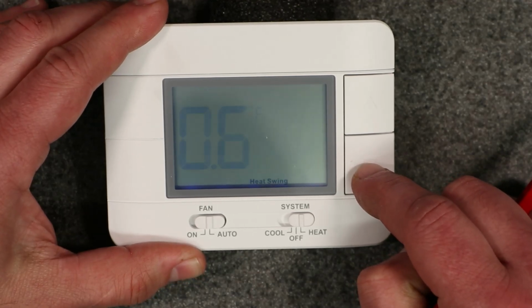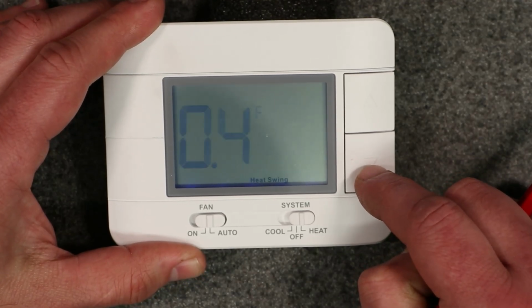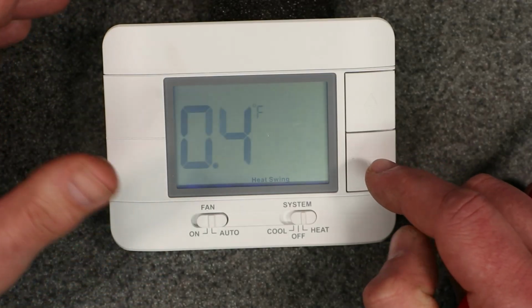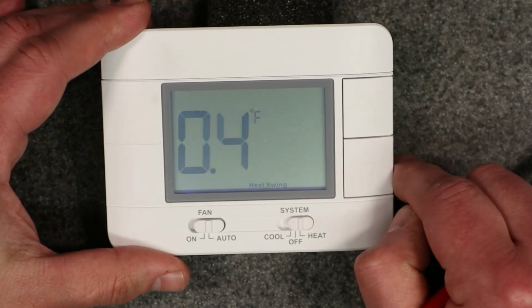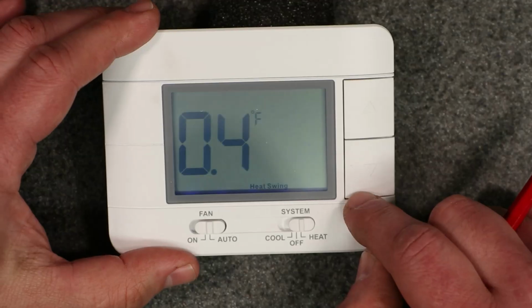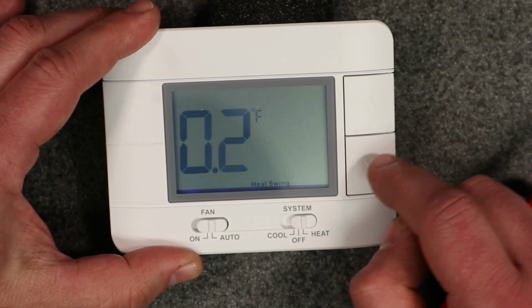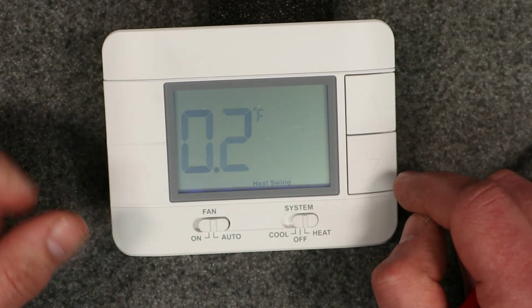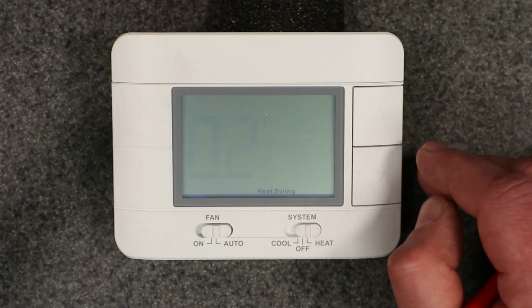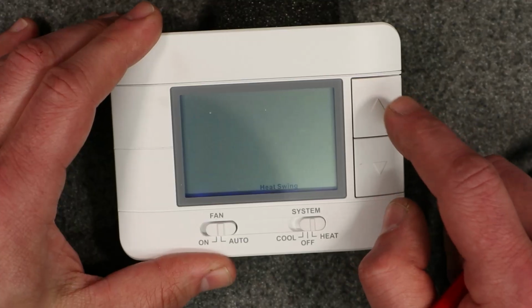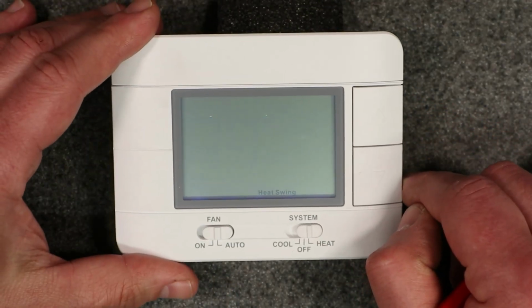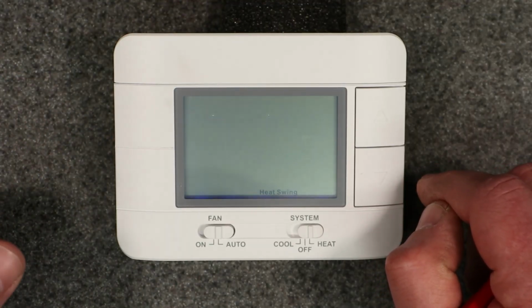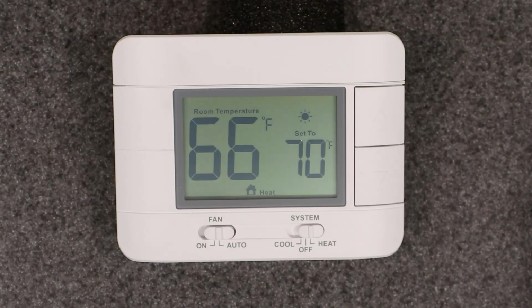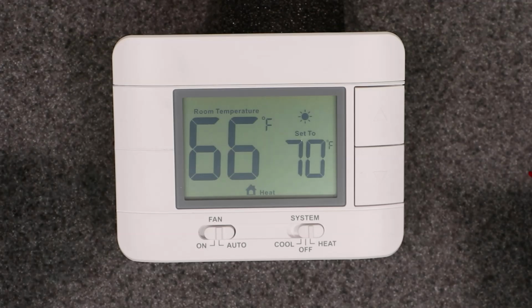Typically you want a pretty tight tolerance on that. I'd go with half a degree, that 0.4 — that would be good for most cases. If you really wanted to go tighter, 0.2 to be dead on that set point, as soon as it hits that set point it's going to turn off or on. So that's basically the tolerancing on the actual temperature sensor, internally when it senses the room temperature.